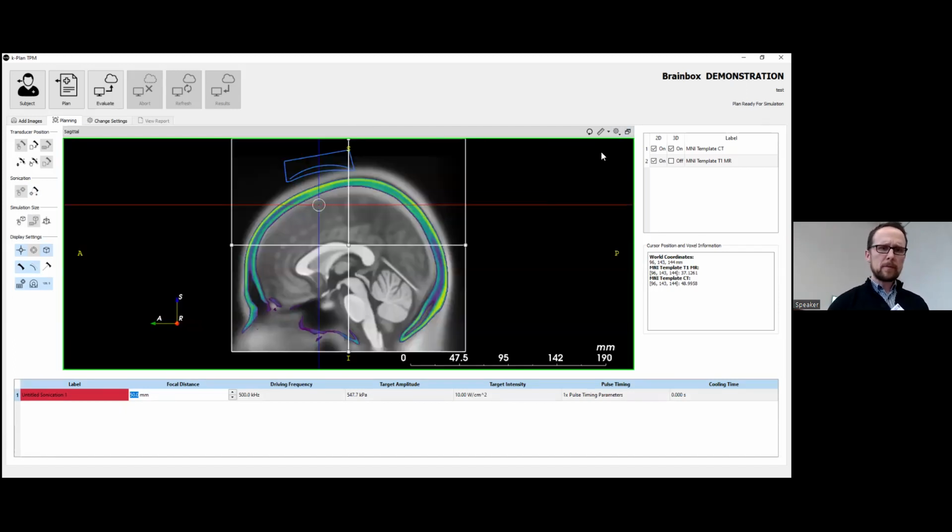So I can measure distance, say from the exit plane or the back of the bowl of the transducer, whatever parameter you need to measure from, to the target area, and that can at least give you an estimate of what you need to put as the focal distance, in this case using a NeuroFUS system, let's say. Click again, so 39 millimeters for argument's sake.